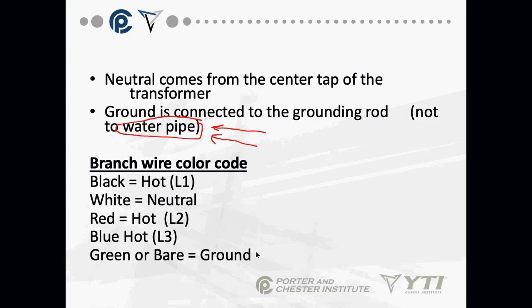If I'm out at a job site, like if I'm on a piece of outdoor equipment, okay, I am going to take one of my hot legs with my meter. I'm going to put one probe on my hot leg. I'm going to put the other probe on the ground wire. What should I get? Nothing. Wrong answer. My meter should get a reading, because my meter is measuring a difference of potential. If my ground is truly grounded, then from L1 to ground, I should get roughly 120 volts. From L2 to ground, I should get roughly 120 volts. If I get zero, then it's not ground. Then I have a problem with my ground. I'm going to be very concerned.